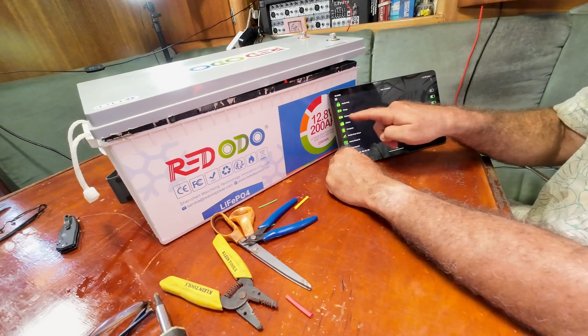So I've turned on charge, discharge, and balance, so it can balance the batteries now. This emergency option, we want to leave off. If you ever got it into a mode where it couldn't work, like over temperature or under temperature, but it was powering a defibrillator and you needed it right now, you'd turn that on and it'll throw its safeties to the wind and give you power. But we don't want that.